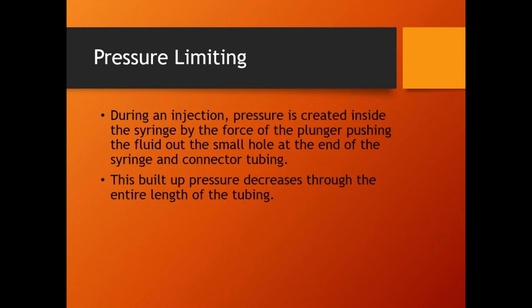Now, what the system is set up to do is prevent destruction to the syringe if we somehow exceed the pressure that this syringe is particularly limited to. Now, this particular contrast goes up to 325. Most CT injectors go up to 300 psi. The other stuff goes to 325. I don't really know why. But 300 is by far the most common. When we're talking about CT and MRI, that's the most common pressure limit we're dealing with. All right.